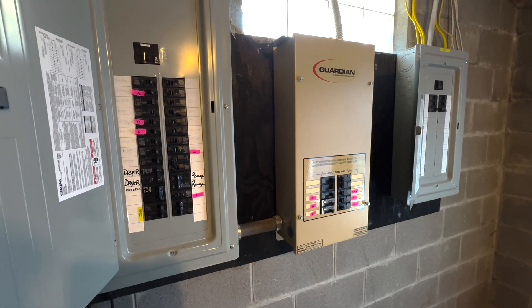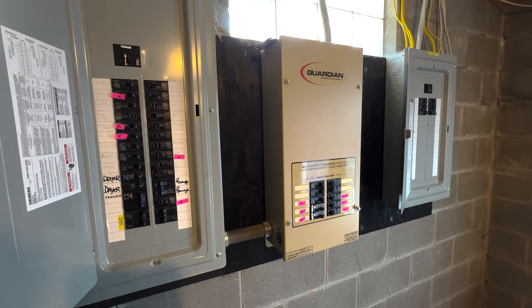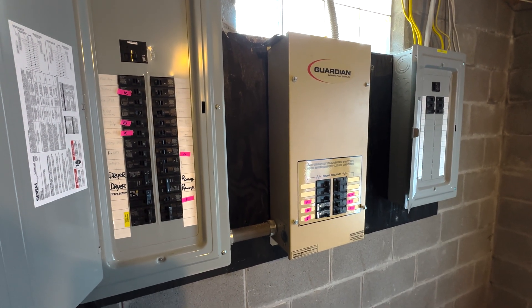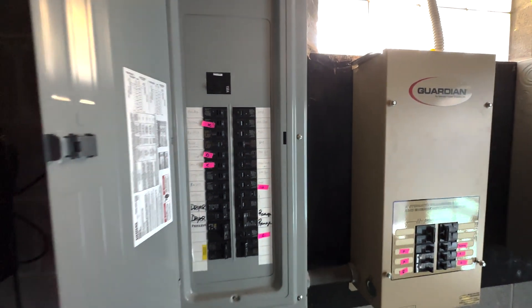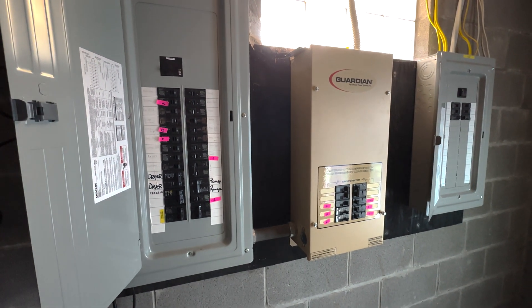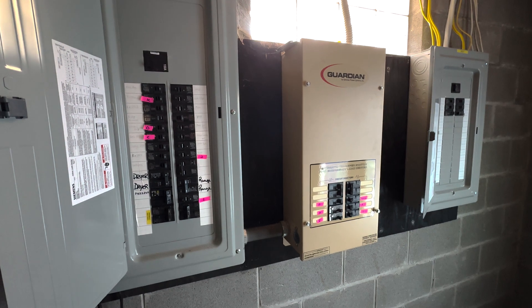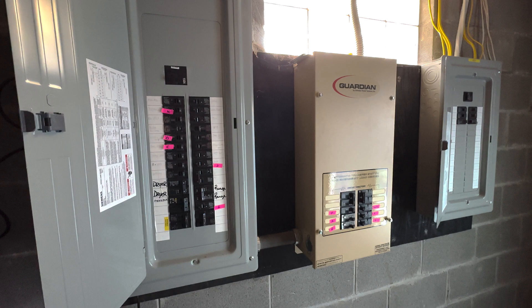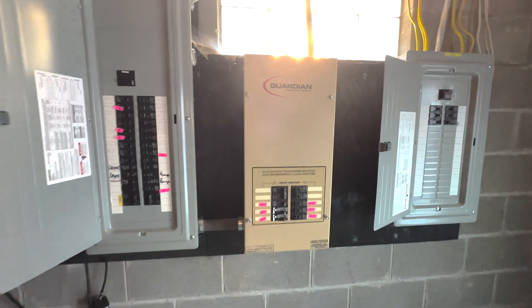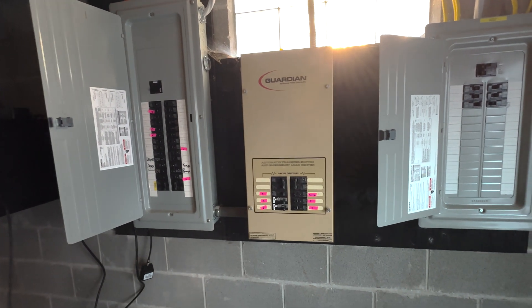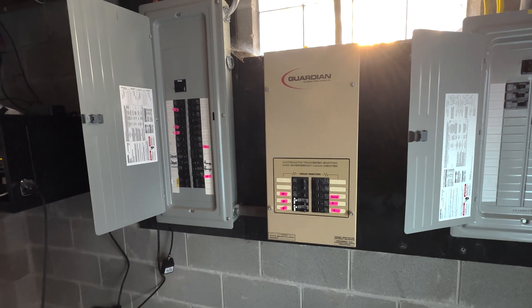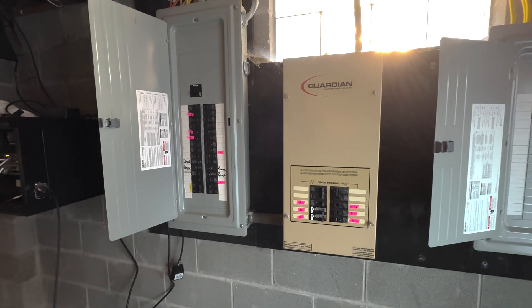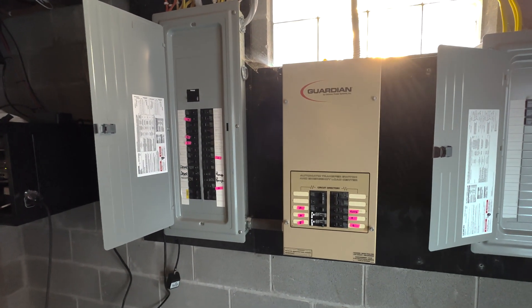Okay. So, let's throw the breaker here and let's get ready for some loud, chunky transfer switch action. So, here we go. That's the UPS. There's the generator starting. Or trying to start. There we go. Now, the transfer switch should click in. There it is. All right. So, now that that's going, let's pull this panel here and see what's energized.